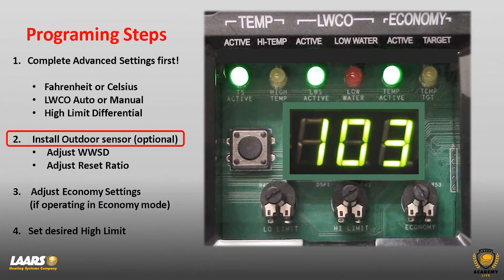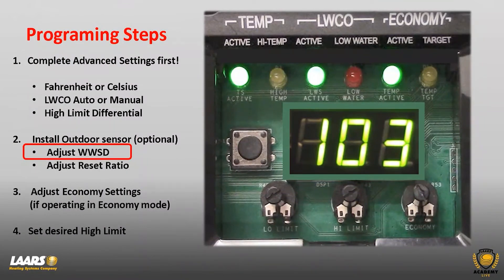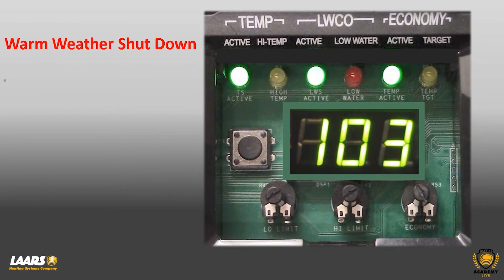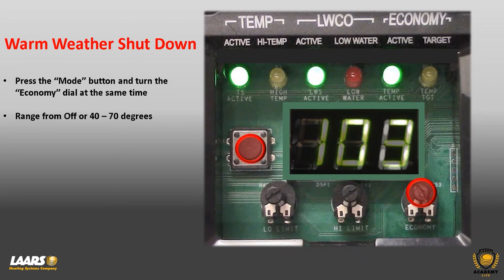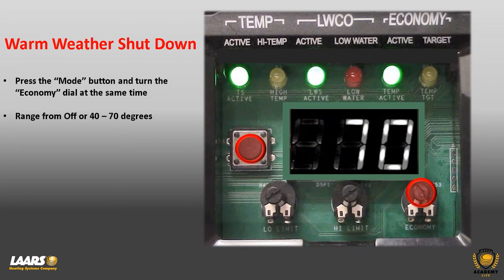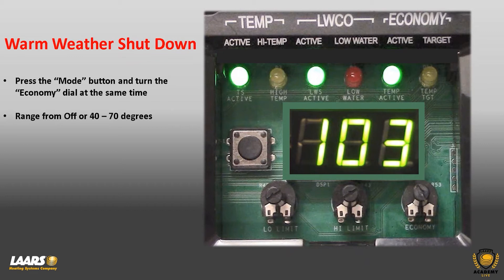Step two: if you chose to install the outdoor sensor, hook it up first. Then you can adjust your warm weather shutdown. Warm weather shutdown is achieved by pressing the mode button and turning the right-hand economy dial simultaneously. The range for warm weather shutdown is from 40 to 70 degrees. In this example, I'm showing a value of 70 degrees, so at anything above 70 degrees the boiler won't operate for heating — though it can still operate for domestic hot water if connected to an indirect.